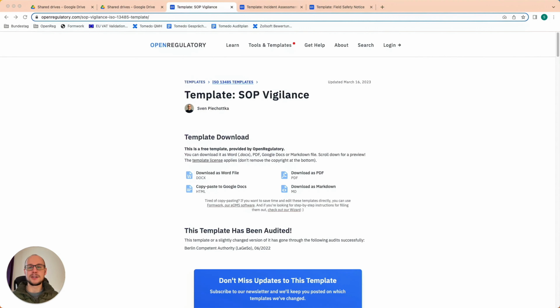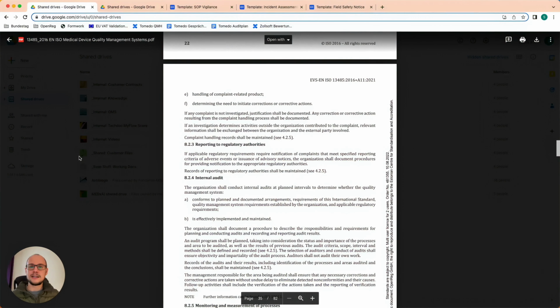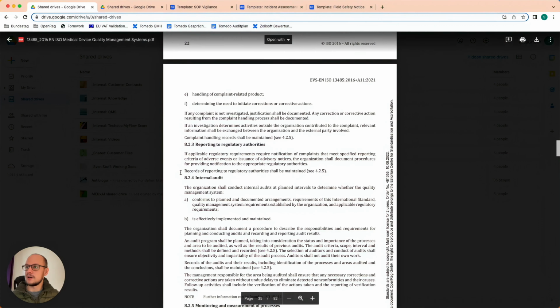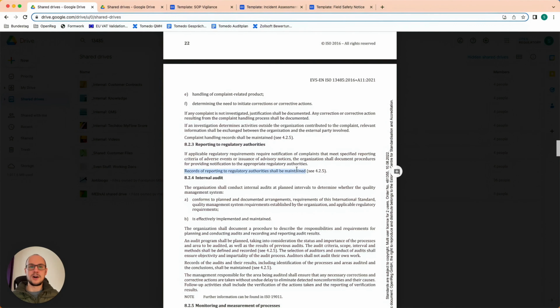In this video, I will only explain a bit better what needs to be done in this process and point you to the few aspects you will need to customize for your organization. And as always, starting out with the regulatory context, there you will actually find very little mentioned on vigilance in the ISO 13485 norm. Paragraph 8.2.3 only requires you to set up a process for the reporting of adverse events or advisory notices to regulatory authorities, as well as for keeping and maintaining records on that.